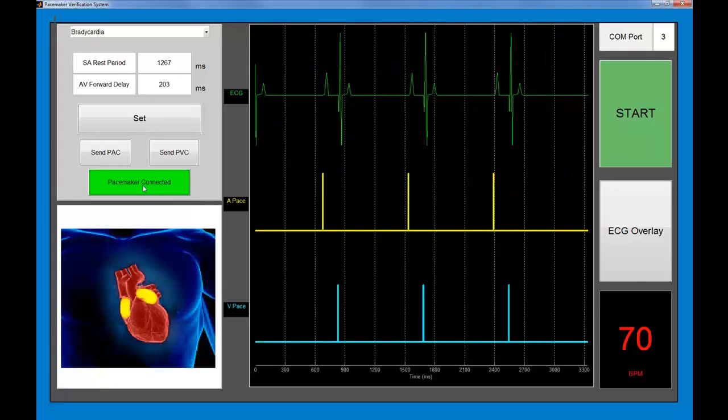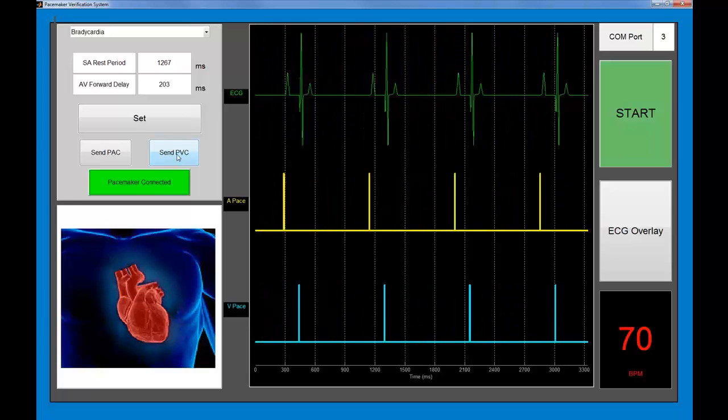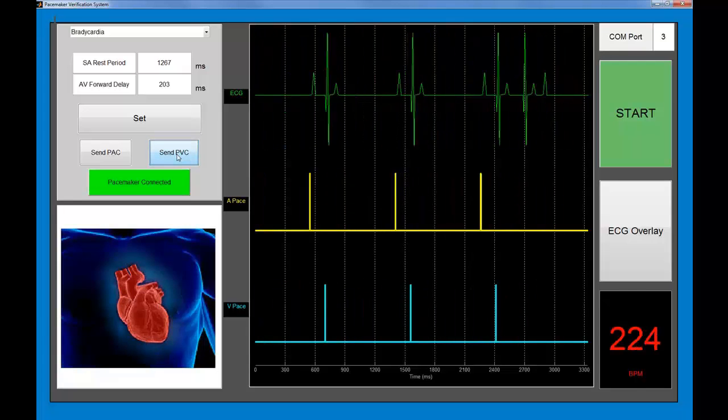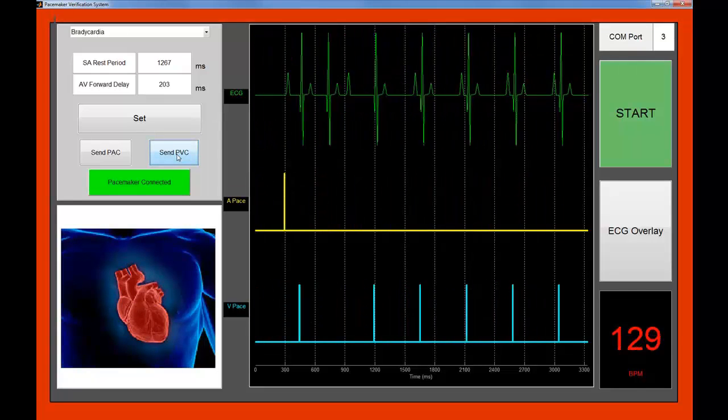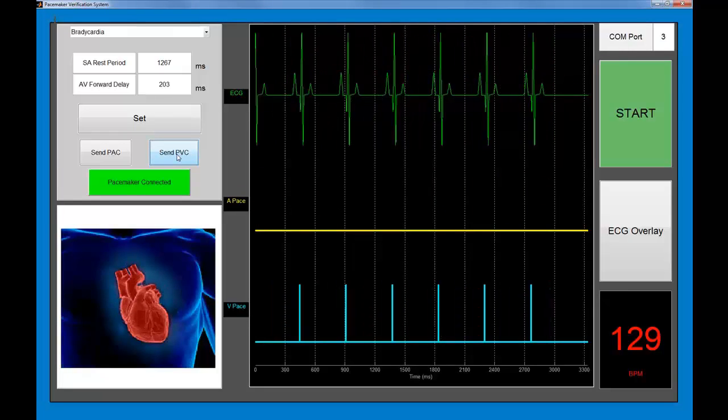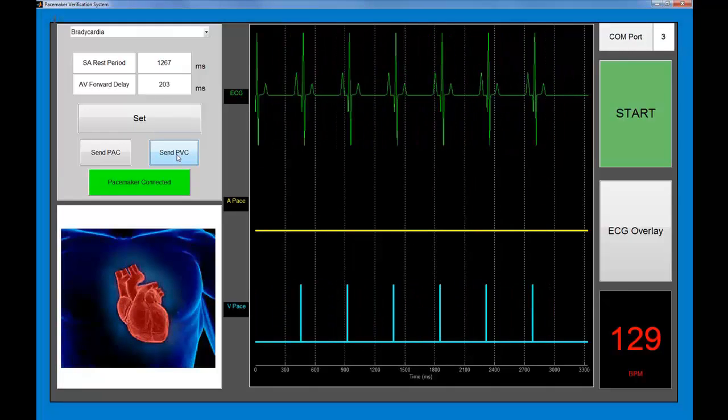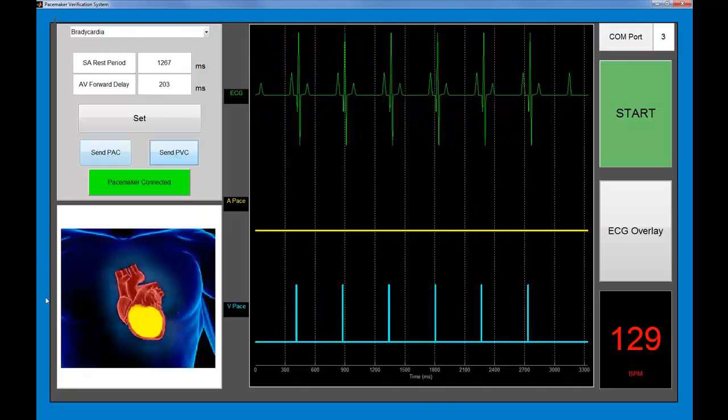So when can a pacemaker go wrong? If the pacemaker is connected at the wrong time, the signal will enter a feedback loop, which drives the heart rate inappropriately fast. This scenario is referred to as pacemaker-mediated tachycardia.